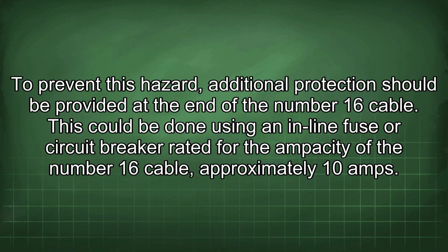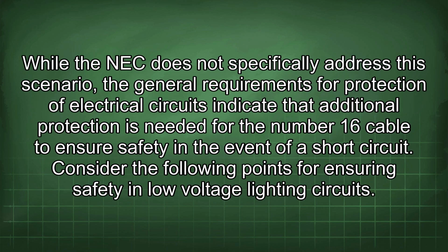To prevent this hazard, additional protection should be provided at the end of the number 16 cable. This could be done using an inline fuse or circuit breaker rated for the ampacity of the number 16 cable, approximately 10 amps. While the NEC does not specifically address this scenario, the general requirements for protection of electrical circuits indicate that additional protection is needed for the number 16 cable to ensure safety in the event of a short circuit. Consider the following points for ensuring safety in low-voltage lighting circuits.